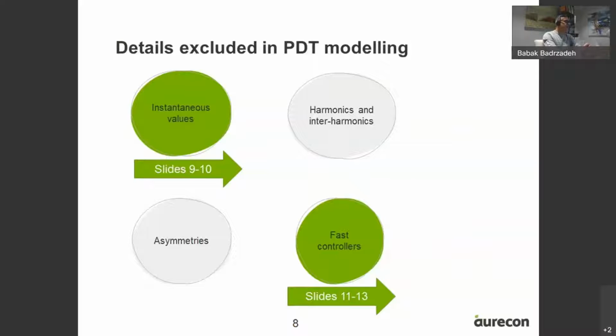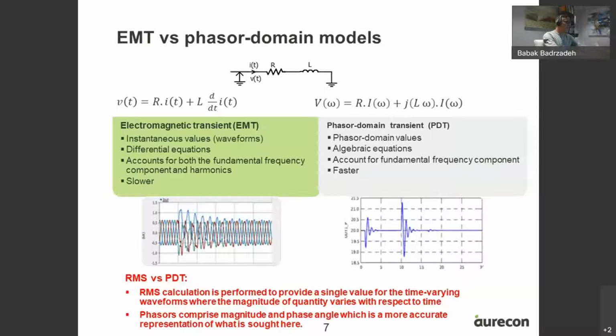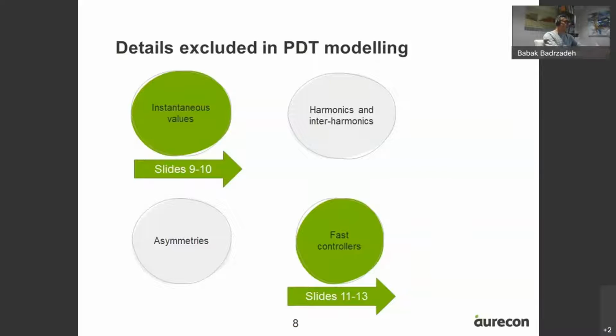The first thing is instantaneous values, which we already discussed in the previous slide, comparing that graph against phasor domain modeling where we don't look at instantaneous values. We already discussed harmonics and interharmonics, and asymmetries, whether steady state or exacerbated during fault conditions. Last but not least are fast controllers. The two components I'll discuss in more detail are instantaneous values and fast controllers, and why they could be important for analyzing a power system with many inverter-based resources.